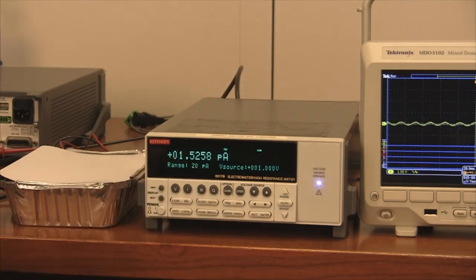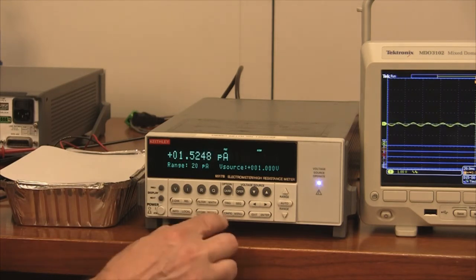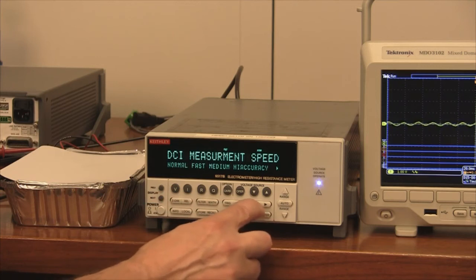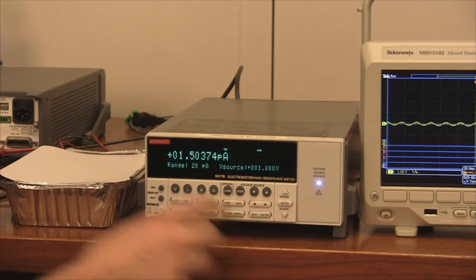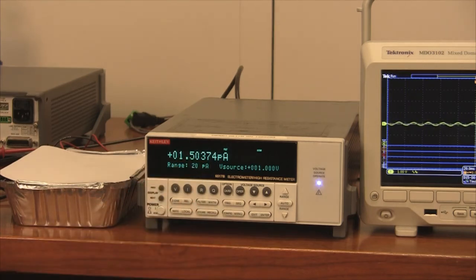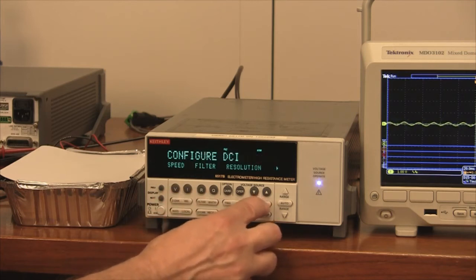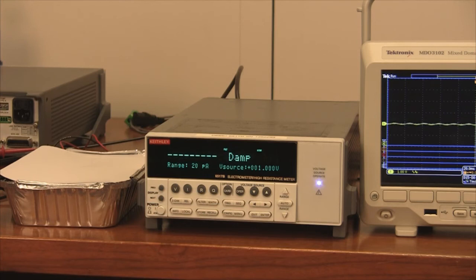Let's see if the PLC, the integration rate, makes a difference. So we'll go to configure I, go to high accuracy. You'll notice that it gives you another digit. There we go. You can see it's much more stable. Like before, we can also add damping, which adds another layer. It's that little jump, and then it'll come back. Well, that's about as stable as you get.